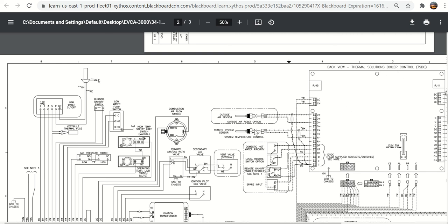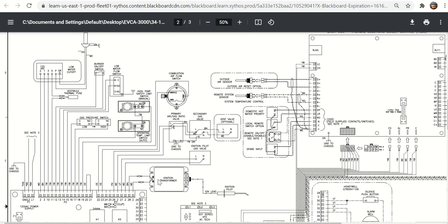It has a system temperature sensor that it can monitor and start and stop and modulate the blower speed based on a set point and the temperature here, but you still have the operating and high limit controls there. Here's the combustion air flow switch. Make sure that the combustion blower is running. Your primary and secondary gas valves, the pilot gas valve, the ignition transformer.